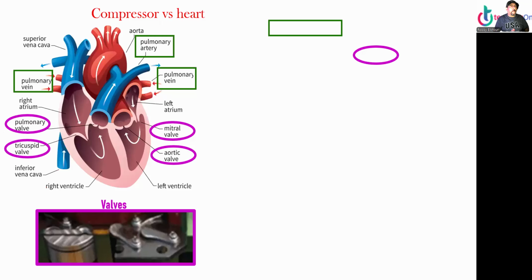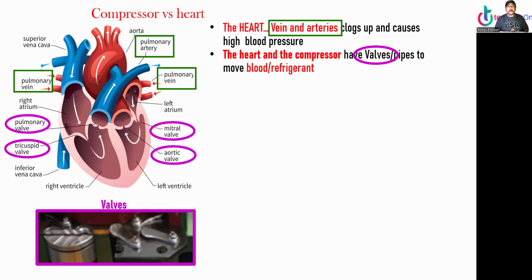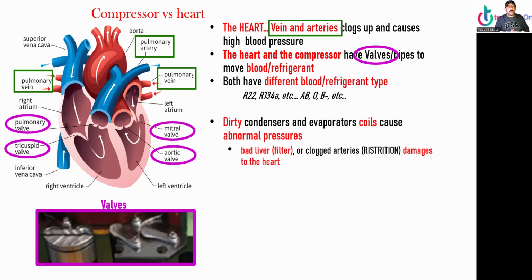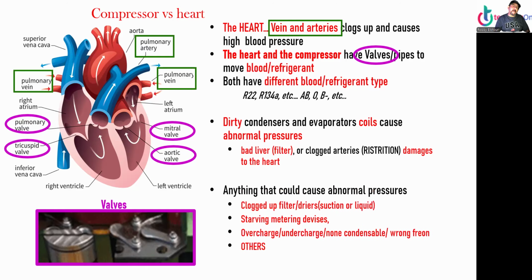Alrighty, now compressor versus the heart. The heart has veins and arteries that plug up and cause high blood pressure. The heart and the compressor have valves and pipes to move blood around and refrigerant. Both have a different blood type or refrigerant type. A dirty condenser and evaporator coil causes abnormal pressure, like a bad liver or filter, or clogged arteries, a restriction. I misspelled restriction. Damage to the heart. Alrighty, so pretty much anything that causes abnormal pressure: clogged filter, dryer, starved metering device, overcharge, undercharge, others.